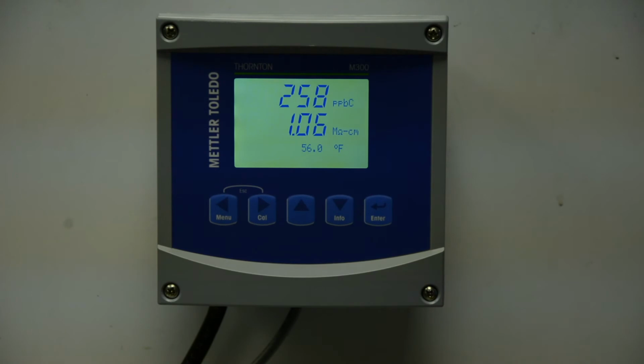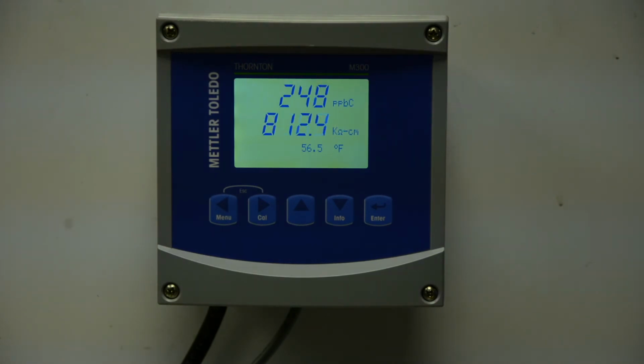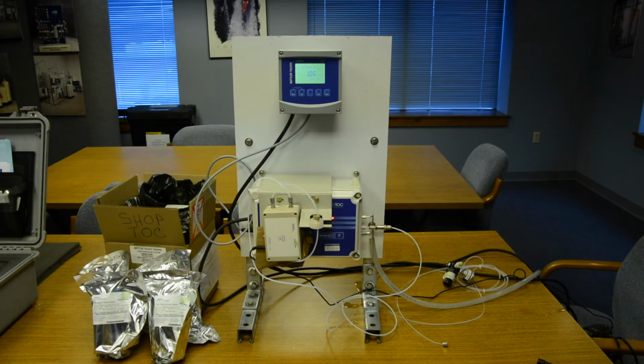The next step is to place your solutions back online. Put your 503 part per billion back online and test it to make sure that it's reading within the limits of plus or minus 50 parts per billion. Then after doing your 500, place your 253 back online to verify that it's reading within a plus or minus 25 part per billion limit. Record those values to verify that your calibration has been successful.